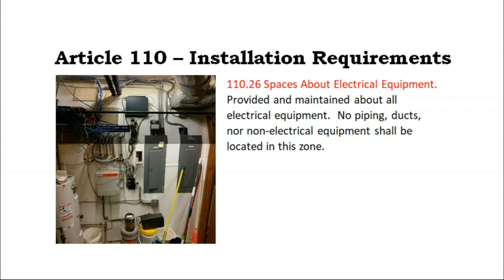When you're planning out your electrical room, the best rule of thumb, if you don't know the code requirements, which are very real, is to imagine a worker standing in front of the equipment fully standing up, not crouching, and working comfortably. That's the space you need in the room for every serviceable part. And none of that space can be shared with other kinds of non-electrical scope, like plumbing or gas. So technically, this air conditioner duct—isn't that HVAC scope, isn't that a shared space? Well, actually it's not, because the shared space is for one person.